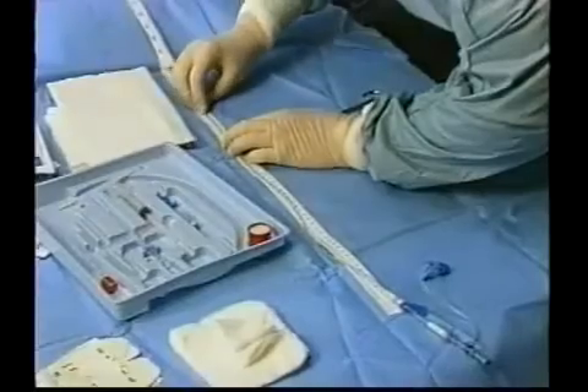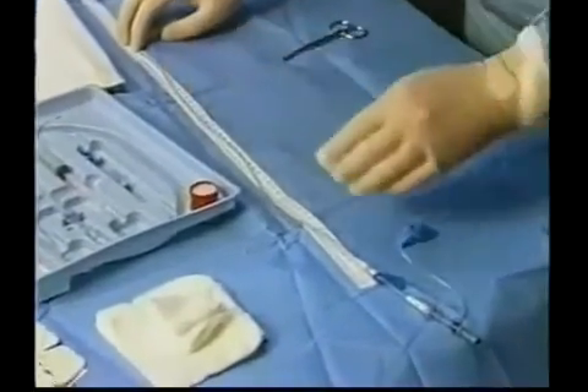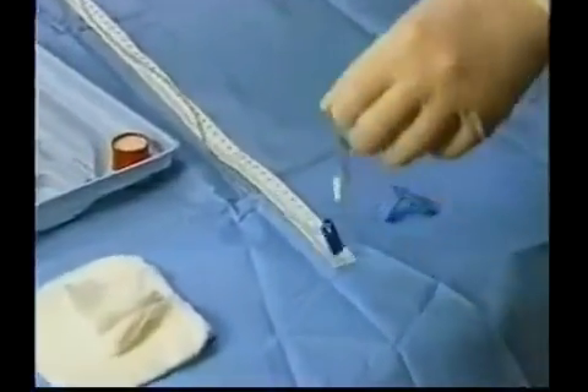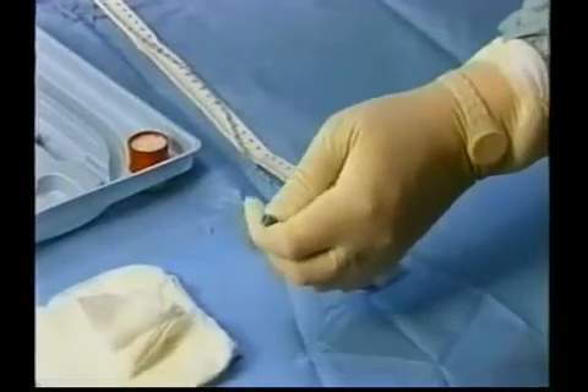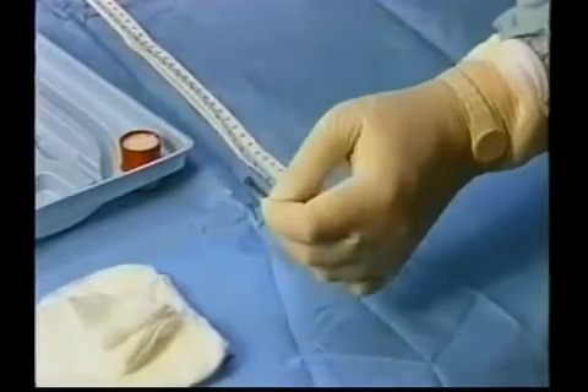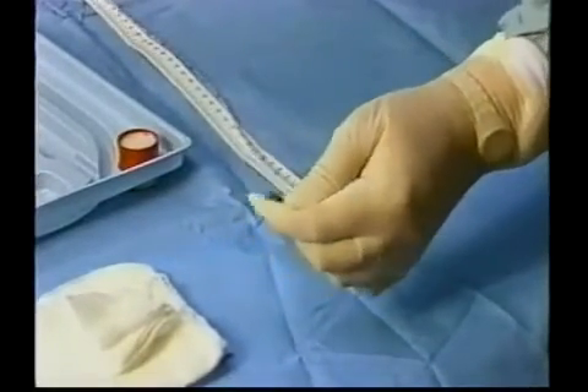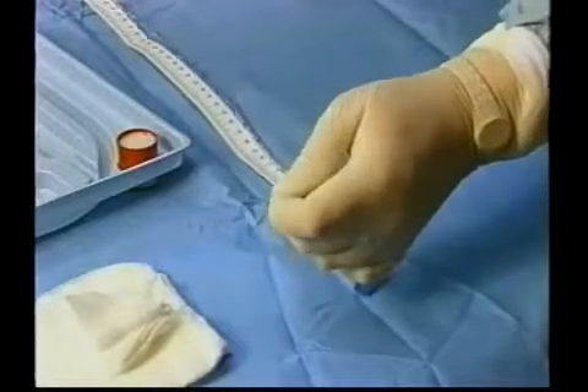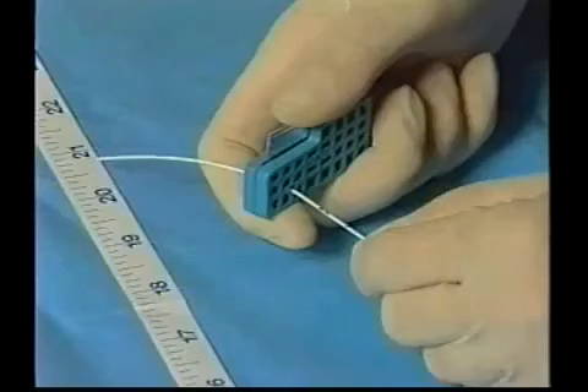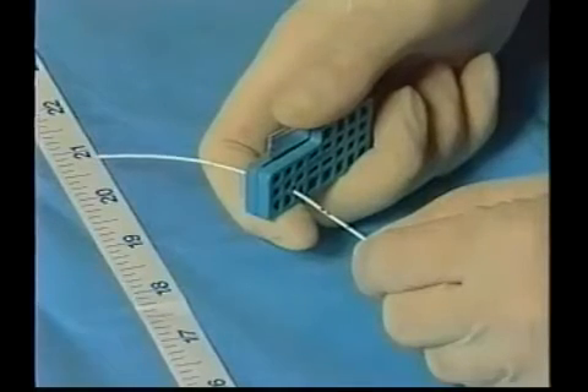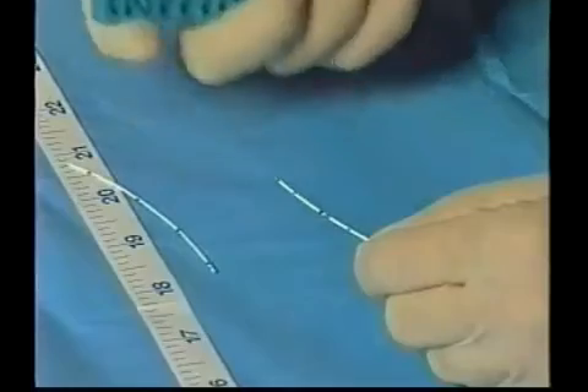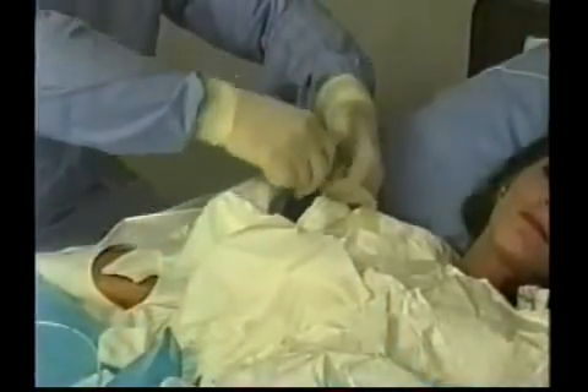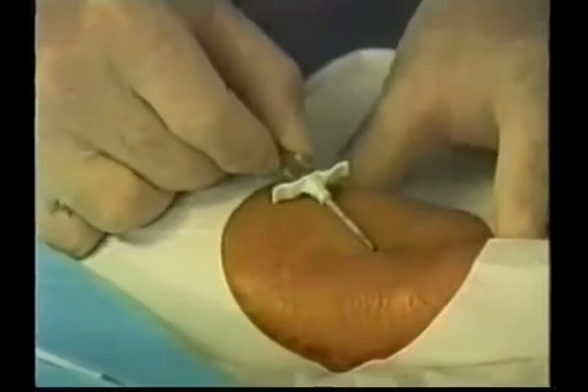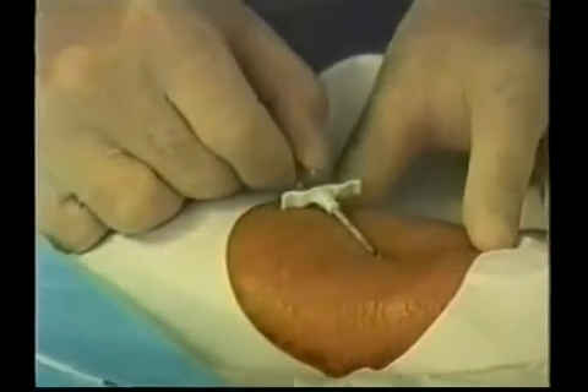When using a trimmable Arrow catheter, retract the placement wire approximately 1 to 1.5 inches further than the point where the catheter is to be cut. Use the sterile trimming device provided and make a straight horizontal cut. Begin the insertion procedure by reapplying the tourniquet, replacing sterile gloves, and performing the venipuncture.